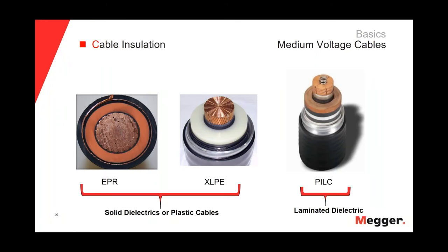In terms of the insulation of the cables, we have two types: solid dielectric or plastic insulation cables, also called polymeric insulation. We are seeing on the left the two most common polymeric insulations — EPR, ethylene propylene rubber, and XLPE, cross-linked polyethylene. On the right, we have the paper-insulated lead-covered cable, in which the insulation is paper impregnated in electrical oil.